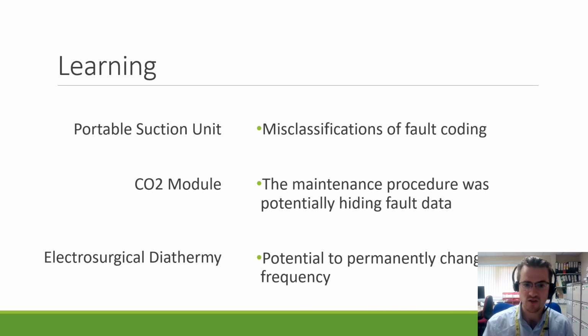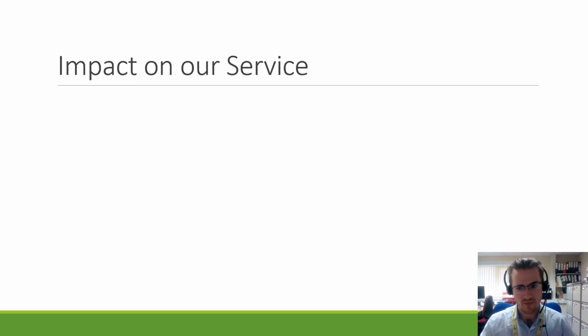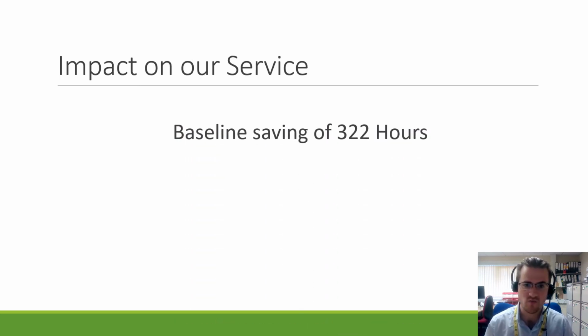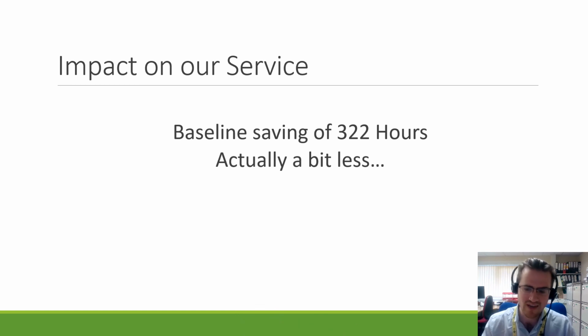And then electrical surgical diathermy. We have the potential to change the frequency to 12 months rather than 6 months to reflect what seems to be the current standard for these devices. And this overall seemed to be much more of a quality learning experience as well as a risk management learning. And this led to an impact on our service of an approximate baseline saving of 322 hours, which is quite a lot, but probably actually is going to be a bit less because some of the planned maintenance was done early, specifically the CO2 modules, more so than we expected.